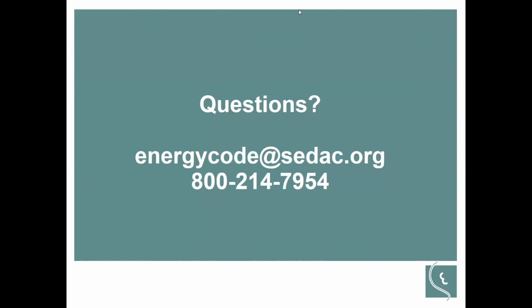Another question came in, and it asked, can you insulate the attic ceiling to comply with insulation above attic ductwork? Ryan? Yes, this is one method. The important portion is that you not only insulate the attic ceiling, but you also insulate over your ductwork for this compliance. You would insulate full depth over the ductwork, so that you end up with a continuous insulation barrier across the entire top.